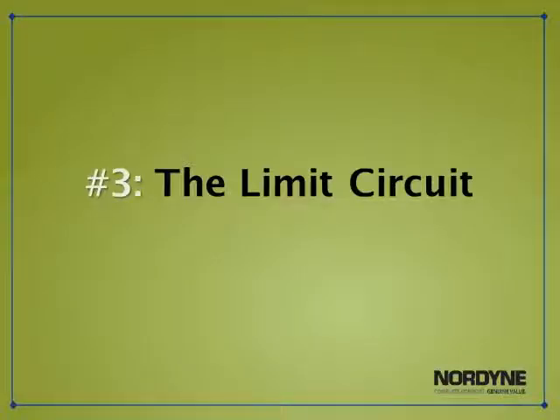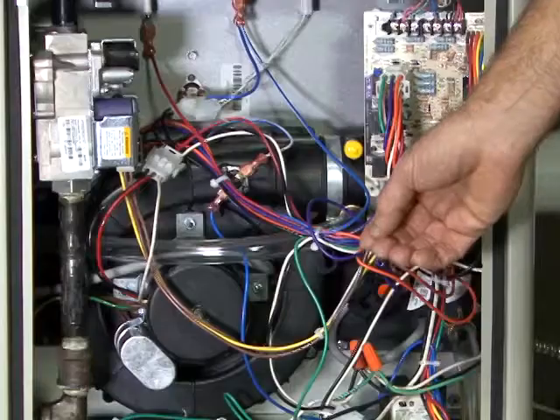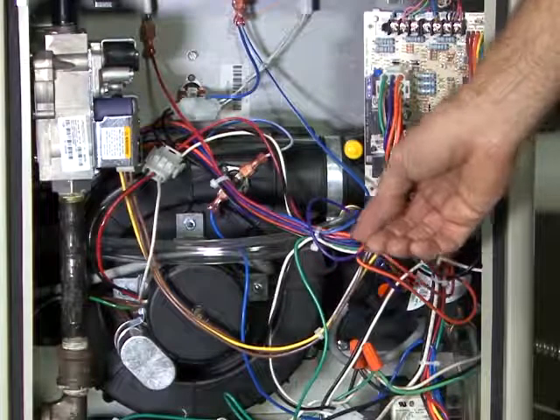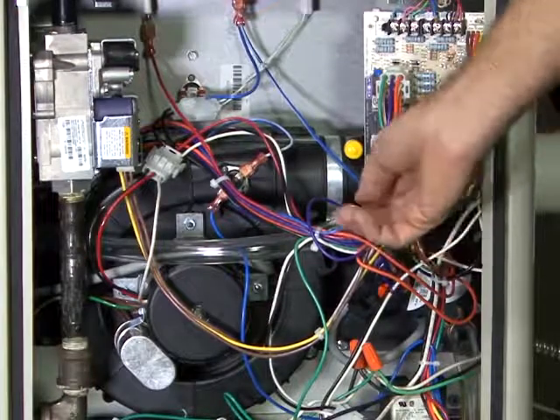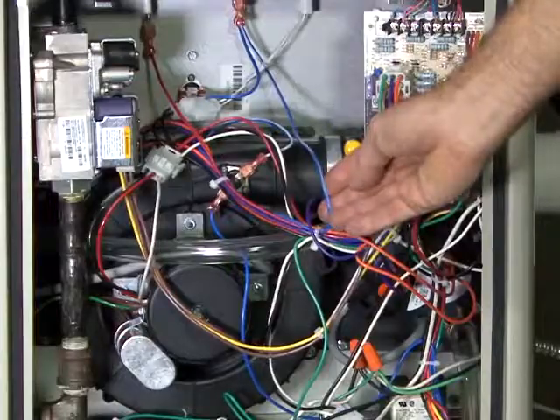The next topic I would like to discuss is the limit circuit. The limit circuit is there to protect the furnace from running at abnormally high temperatures within the furnace cabinet or within the furnace heat exchanger. All the limit switches in the limit circuit are wired in series on the blue wire that goes back and connects to the control board. This blue wire is powered by 24 volts from your interface control board.